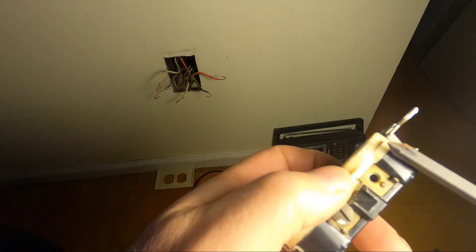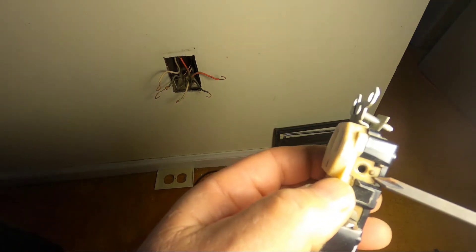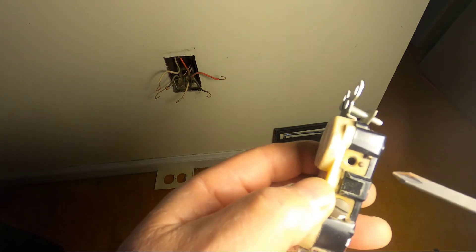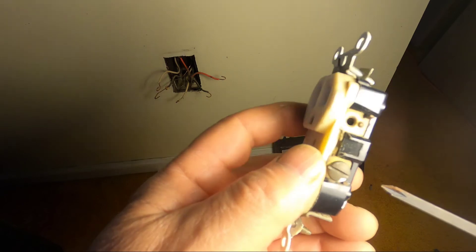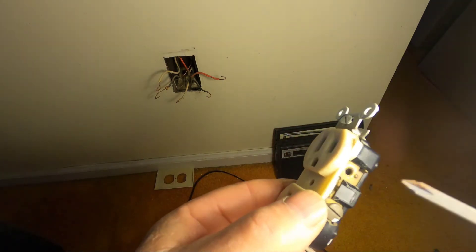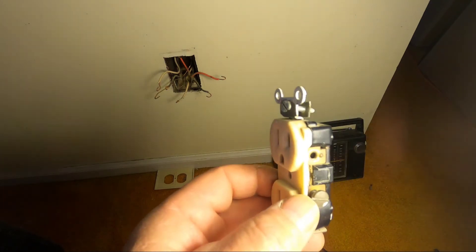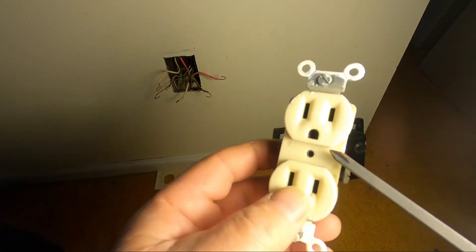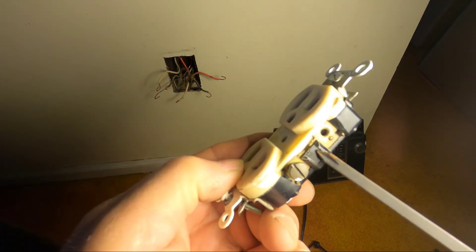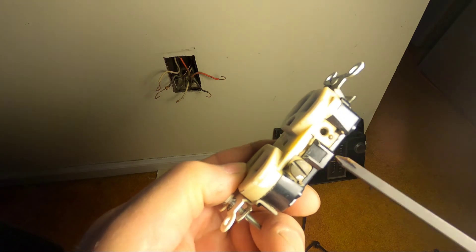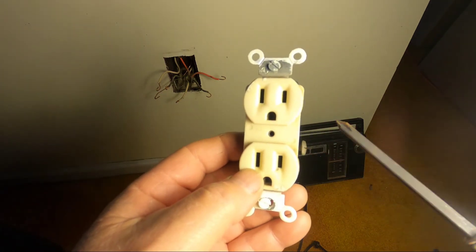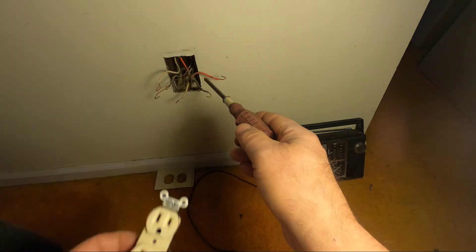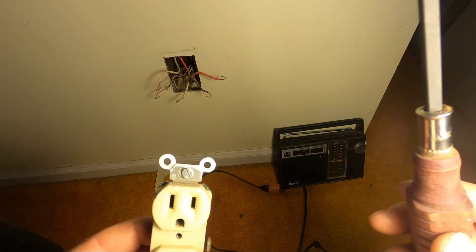On the power side, where the current's coming in, you can see that tab that was over here was broken off. The reason for that is the power coming to the top receptacle is not feeding the bottom. The link is broken. Power coming to the bottom one is fed from a different line. That's why we have all these lines over here.